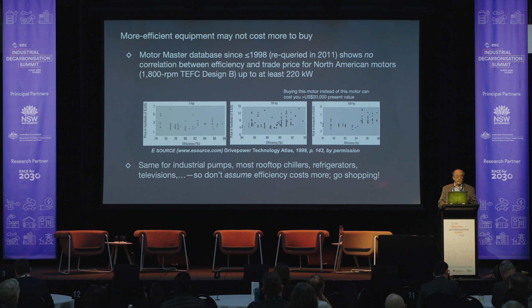So around 1998, you could buy the most efficient 100 horsepower asynchronous motor cheaper than nearly the least efficient ones with otherwise comparable specifications, and that would save you upwards of $20,000 US present value per motor. I suspect this is still true, and it's true of a lot of other things — common industrial pumps, most rooftop chillers, and a lot more. So don't assume that efficient kit must cost more.